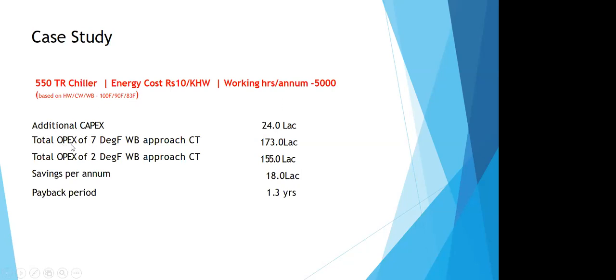And we compared the operational expense of the traditional tower and the low approach tower. For the 7 degree approach, we are getting roughly 173 lakhs as the running cost for this particular case. If you look at the 2 degree approach, we get a running cost of 155 lakhs. So there is a saving of roughly 18 lakhs by using a low approach cooling tower, and the extra cost that one has to pay is roughly 24 lakhs. So this extra cost can be recovered in less than 1.5 years' time. You have a payback of roughly 1.3 years. So the extra cost of the low approach cooling tower can be recovered easily within less than 2 years.